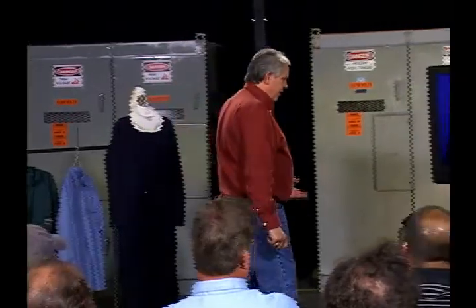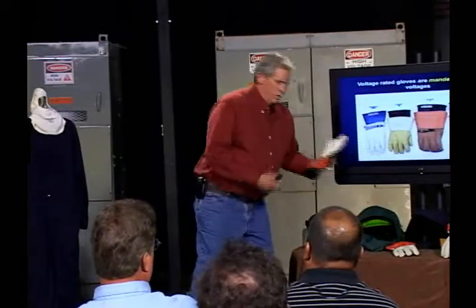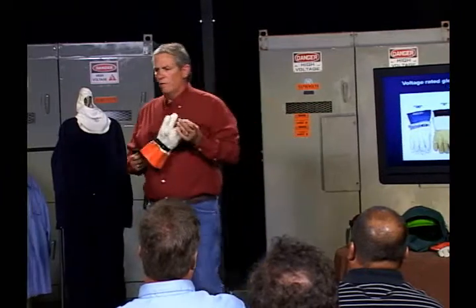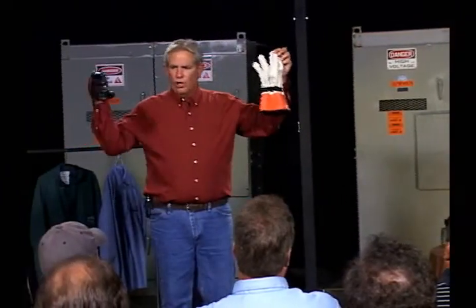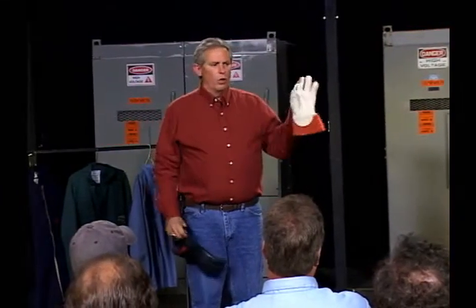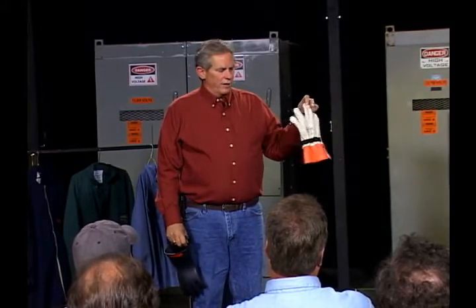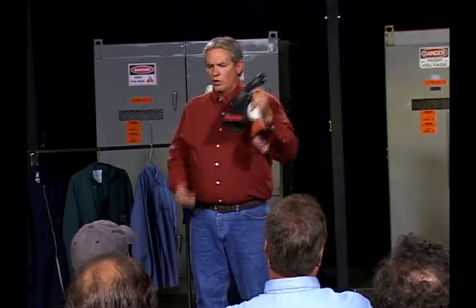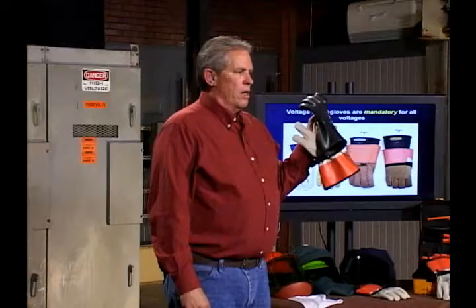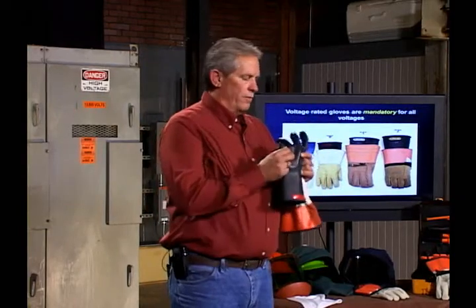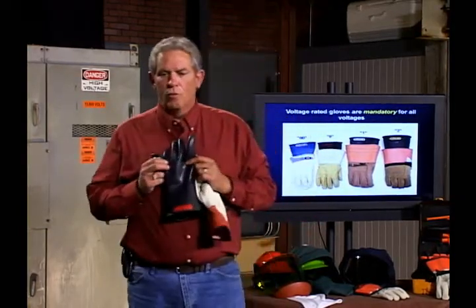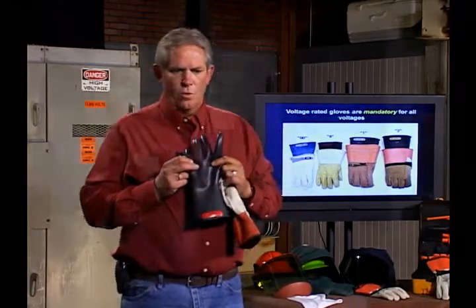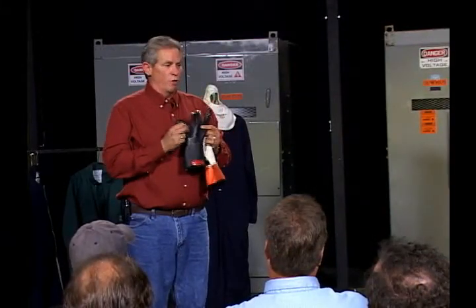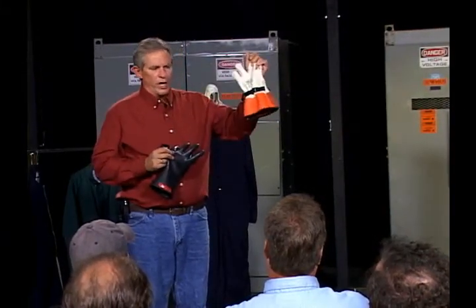The leather protector that's over the glove must stay with the glove. It is designed to protect the rubber glove itself. It is not a work glove. You cannot take this glove and go out and cut a bunch of all thread and then go back and put it on your rubber gloves. You just contaminated your rubber glove. A small pinhole in this rubber glove will get you killed. Electricity will find it. So we have to do a good job of inspecting the gloves before we use them. We want to make sure our leather protectors are kept with the gloves and are not used as work gloves.